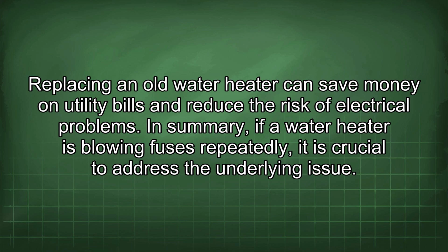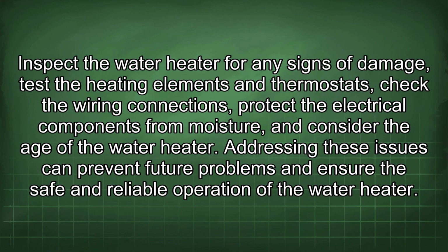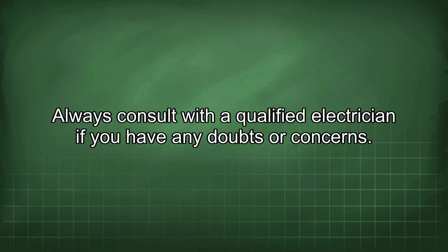In summary, if a water heater is blowing fuses repeatedly, it is crucial to address the underlying issue. Inspect the water heater for any signs of damage, test the heating elements and thermostats, check the wiring connections, protect the electrical components from moisture, and consider the age of the water heater. Addressing these issues can prevent future problems and ensure the safe and reliable operation of the water heater. Always consult with a qualified electrician if you have any doubts or concerns.